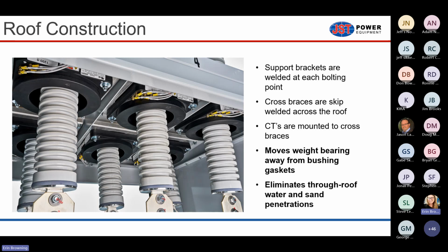So to prevent flexing and bowing of the roof, we welded in crossbars. That's what you see here. And the crossbars actually are responsible for supporting the weight of the CTs and the bushing so that you don't have an excess amount of weight on the roof. These are welded into the cabinet.